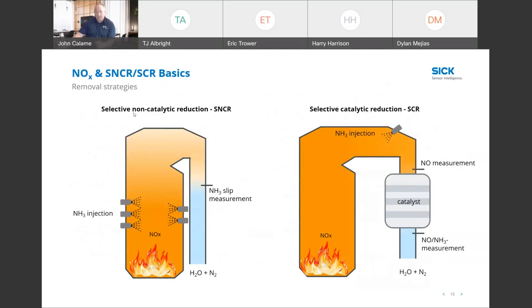So to explain the two just briefly, the selective non-catalytic reduction is using direct ammonia injection to convert the NOx to water and nitrogen. The selective catalytic reduction is using not only ammonia injection, but a catalyst. So you inject the ammonia prior to the catalyst, react all the NOx that's in the stack, and then convert that to water and nitrogen.